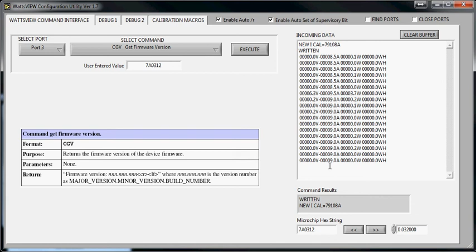So now you can see it's saying 9.0 amps. That's minus 9.0, because we looped the wire through the sensor starting from this direction, so it's negative. If we route the wire the other way, starting through that way, it'll be a positive 9.0 amps. So that's how you adjust the current calibration setting for the WattsVIEW sensor.